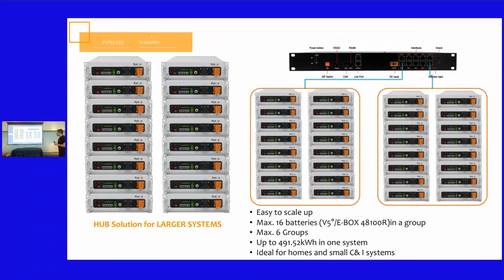This is our hub for the big system. As I mentioned, the V5 can do a 491.52 kilowatt hour system. So when you install over 16 pieces of battery in a group, you need a hub for the V5, and you can install 6 groups of the V5 to do a light commercial system of about 500 kilowatt hours.